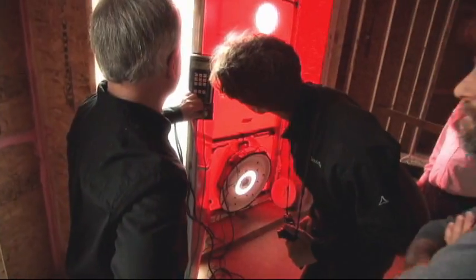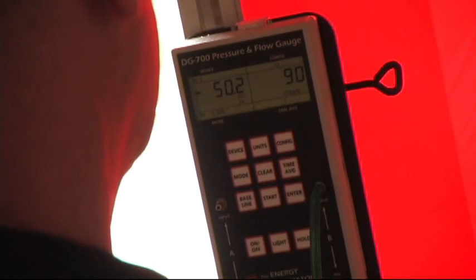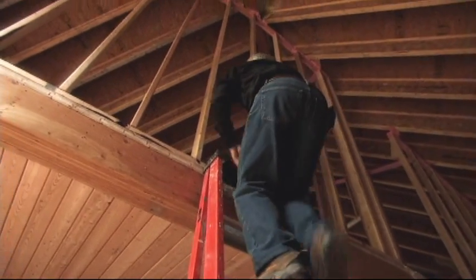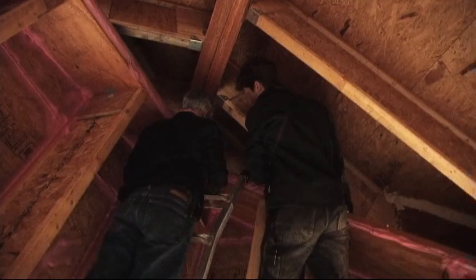One of the Passive House standards is that it has to be sealed very tightly. The lowest reading I've ever had is 91. We're doing a preliminary blower door test, checking for infiltration before the insulation is installed — checking to see how well the house is air sealed. I can say right now this is the tightest house I've ever tested in over a dozen years. We'll be checking all the duct work, air infiltration, and conducting health and safety tests. This house still has a whole range of things to accomplish before it can be certified.